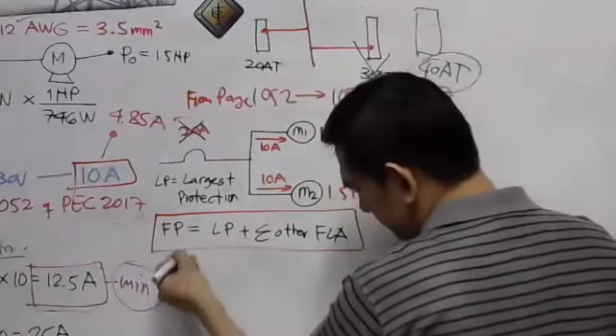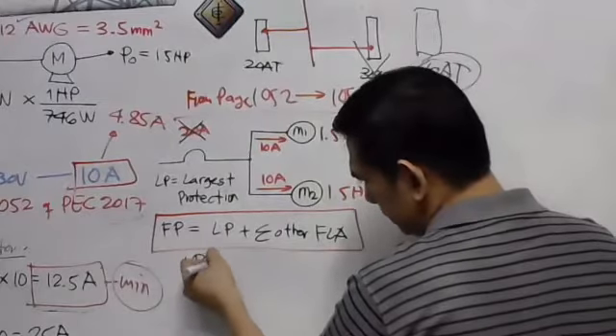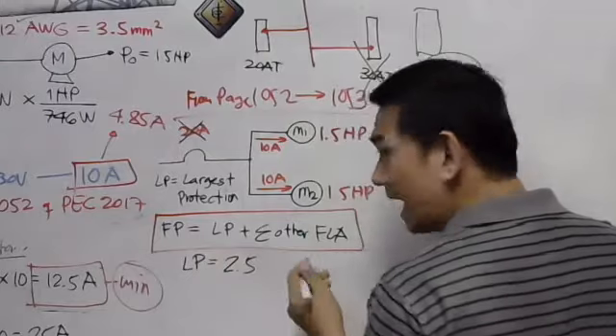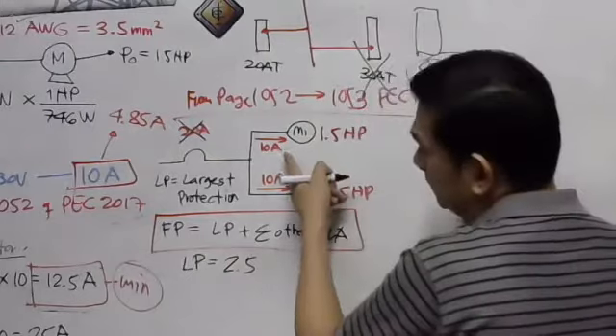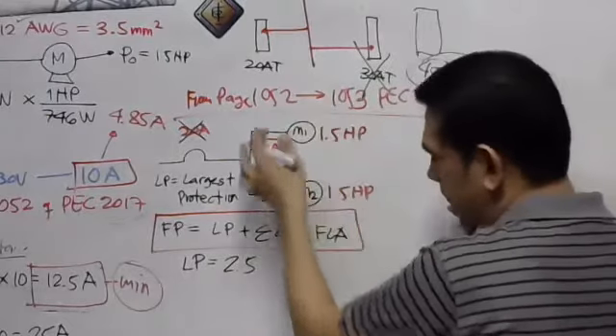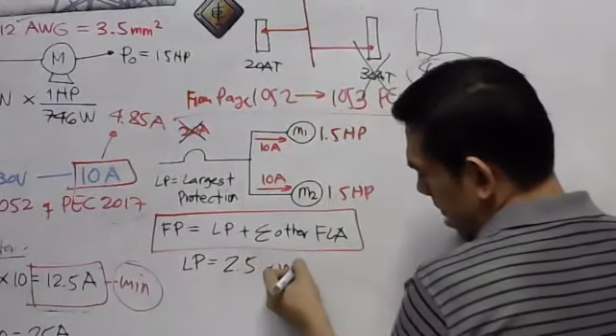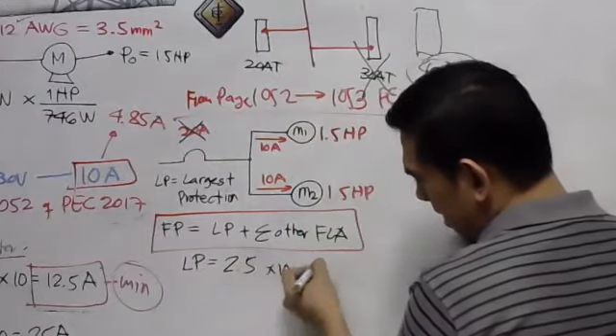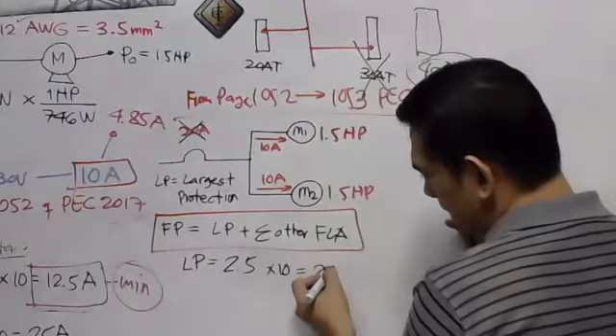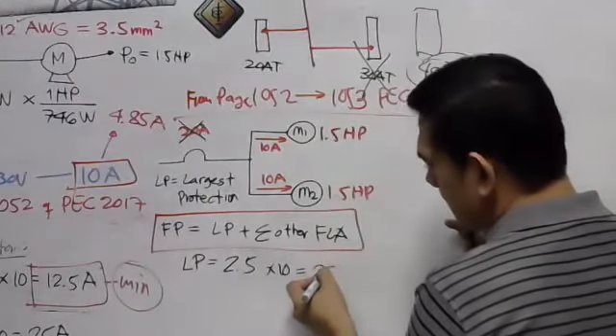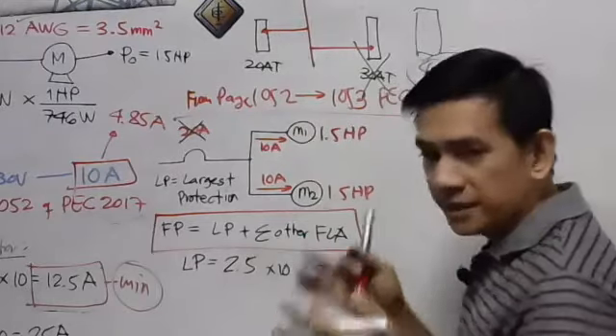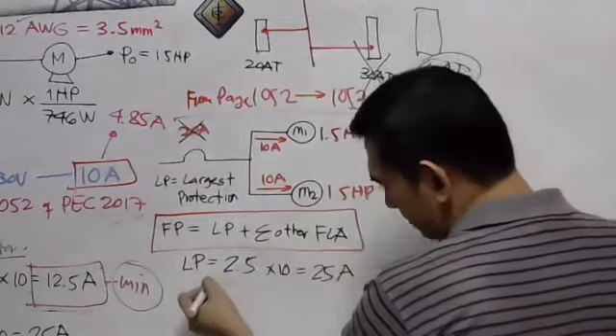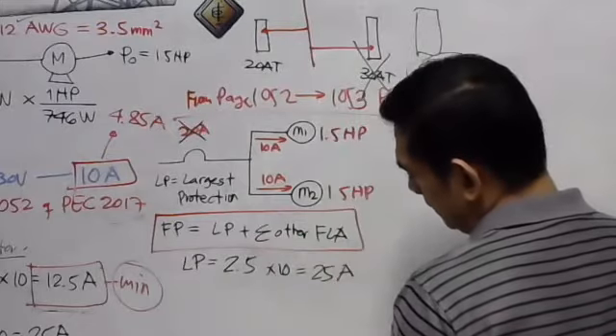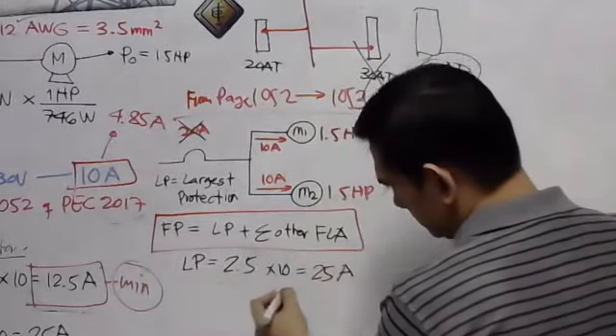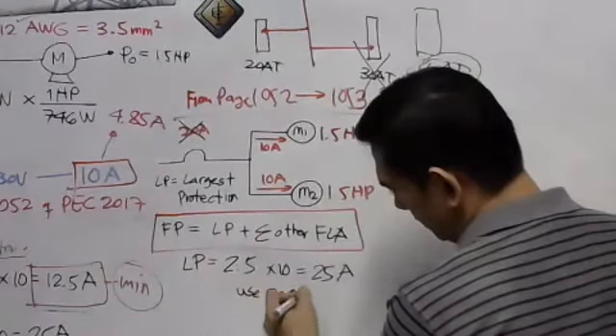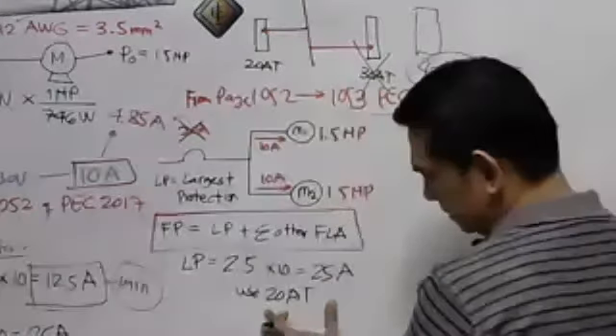But the largest protection is this. The largest protection is equal to 2.5 of the larger ampere. But for this case, there is no larger ampere. Well, you can choose, let's say, for motor 1, times 10. Okay? So this is how much? 2.5 times 10, that is 25. No? 25 ampere. Okay, I taught you before, you can make use of the 20 ampere. Okay, that is, let's say, 20 ampere. Therefore, use 20 ampere. Trip circuit breaker can be used. Okay.